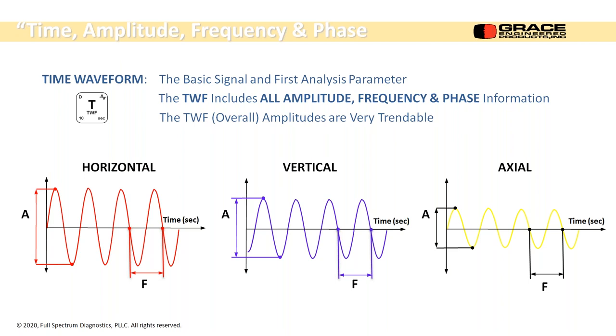Simultaneously, the interesting feature as far as what we're concerned with right now is tracking the amplitude. So I have a horizontal amplitude, vertical amplitude, axial amplitude, and I'll have three different trend lines that I can run statistics on. I can also calculate the frequency, okay? We'll get to that in a second, but the frequency won't be a parameter that we're interested in until there's some amplitude excursion telling us that there's a problem.